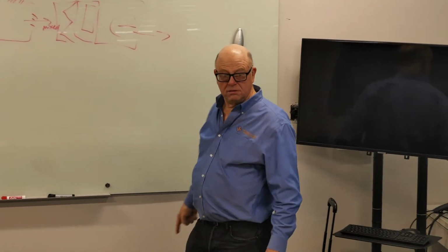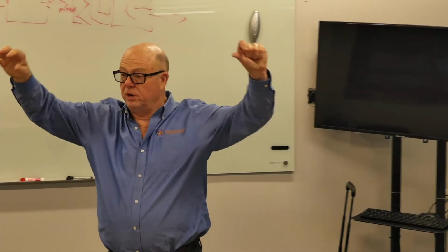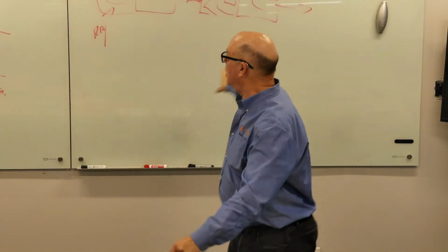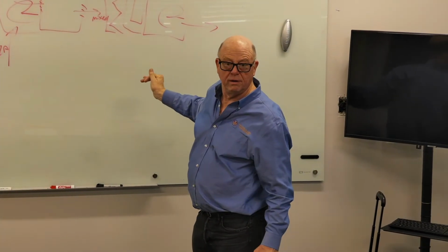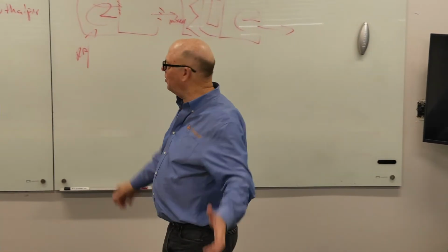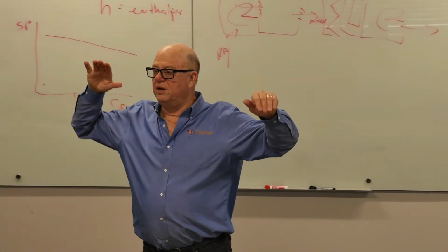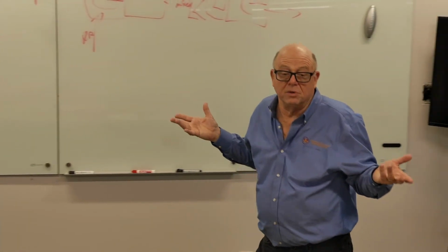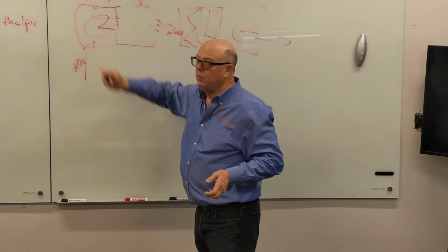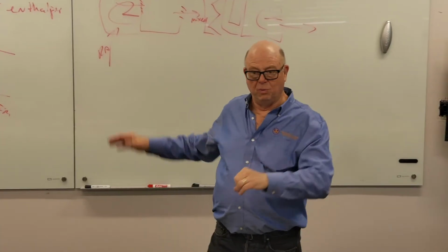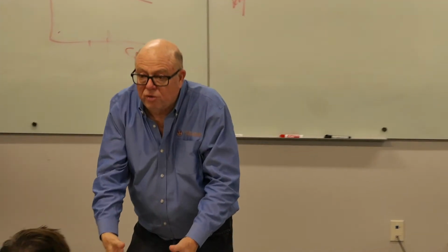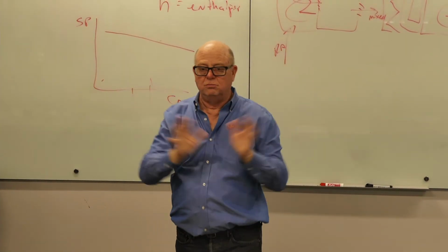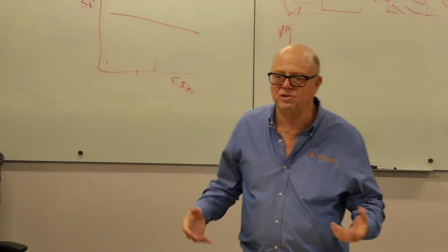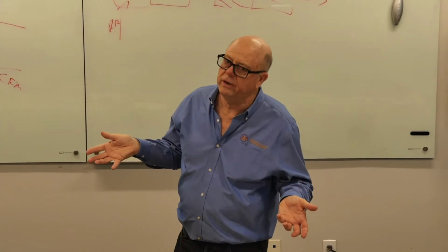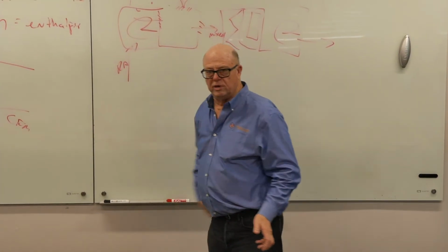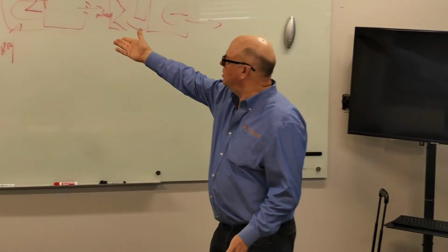The supply fan needs to be controlled to maintain duct pressure, to get air to all these things, right? We already talked about how you control a supply fan. But how do you control the return fan? Because back in the day, they both would have had inlet vanes. Now they have variable speed drives. See, the relief fan was easy, right? We looked at the pressure in the lobby, we compared it to the outside, and it was simple. Not only simple, but it very seldom went bad because it was simple. Simple is good. How do you control a return fan with an extensive duct system? What signal do you give it?